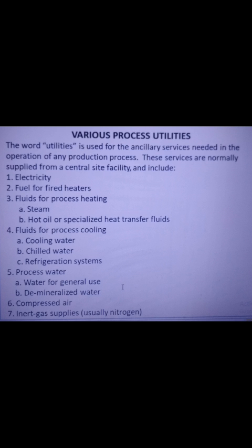Now I will tell you about the fired heaters. The fired heaters are used for process heating duties above the highest temperatures that can be reached using high pressure steam, typically about 250 degrees Celsius. The process streams may be heated directly in the furnace tubes or indirectly using hot oil circuits or heat transfer fluids.